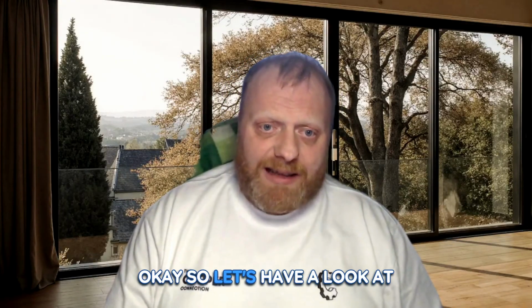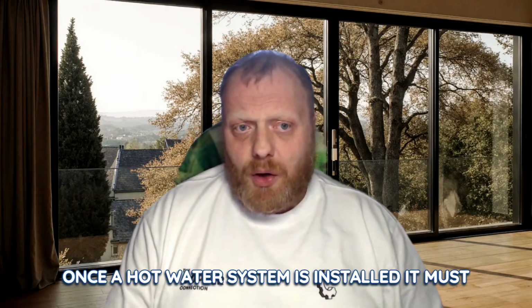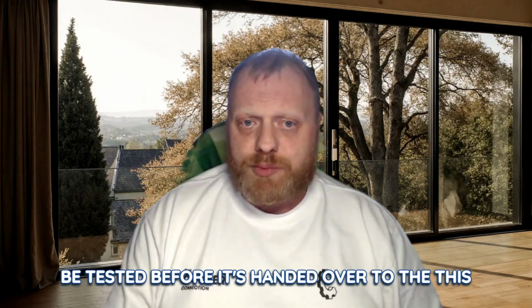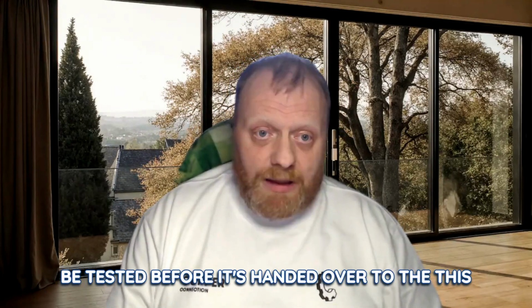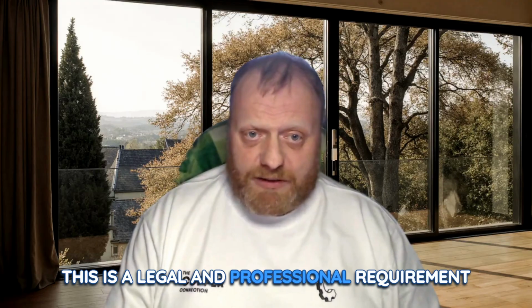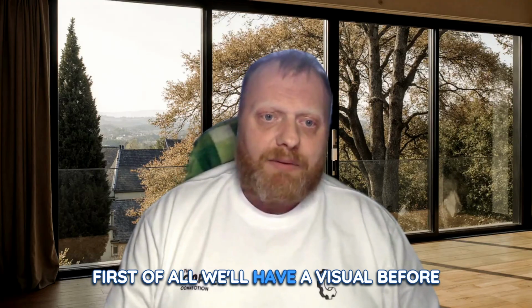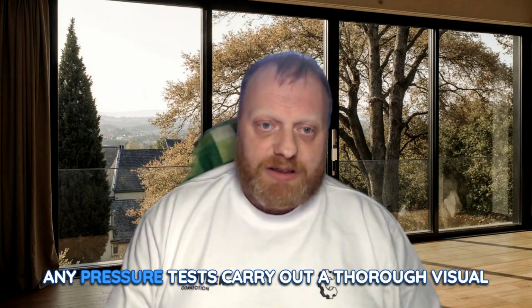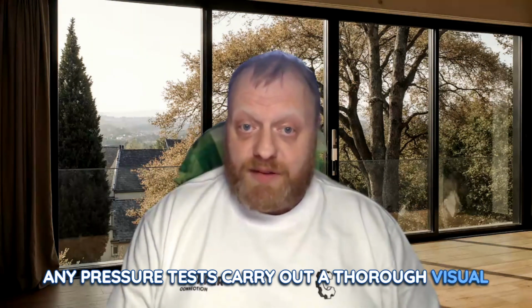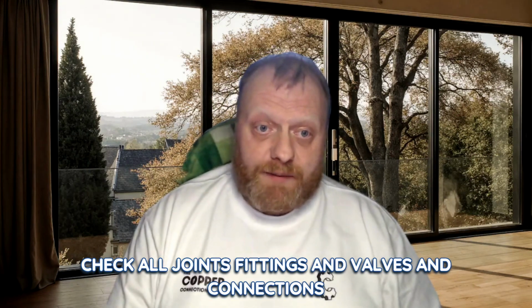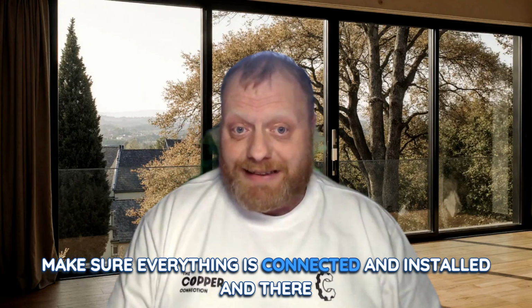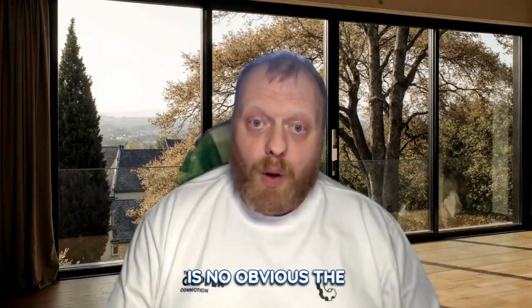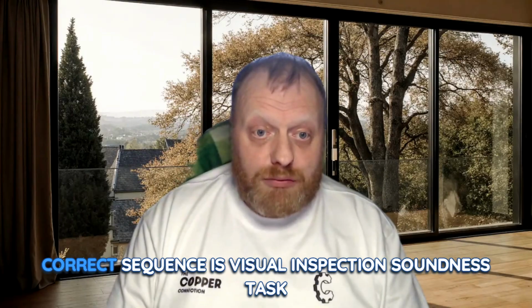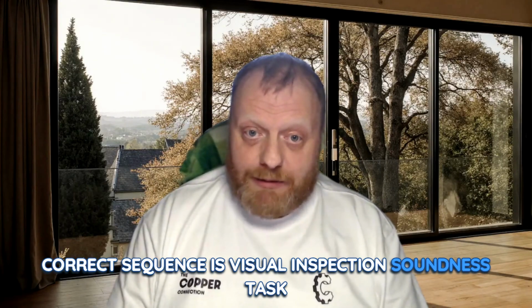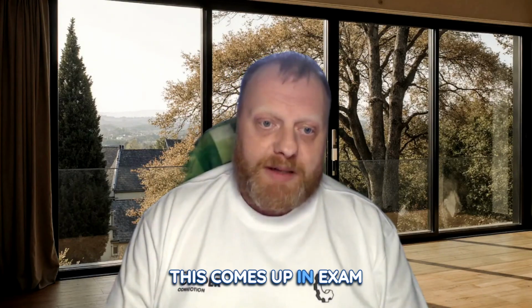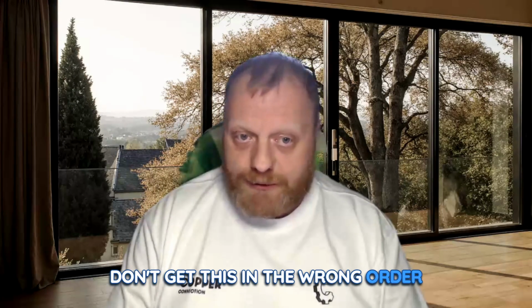Okay, so let's have a look at commissioning and testing. Once a hot water system is installed, it must be tested before it's handed over to the customer. This is not optional, this is a legal and professional requirement. First of all, we'll have our visual inspection. Before any pressure tests, carry out a thorough visual inspection. Check all joints, fittings, valves and connections. Make sure everything is connected and installed and there are no obvious issues. Exam tip, the correct sequence is visual inspection, soundness test, flush system. This comes up in exams, don't get this in the wrong order.